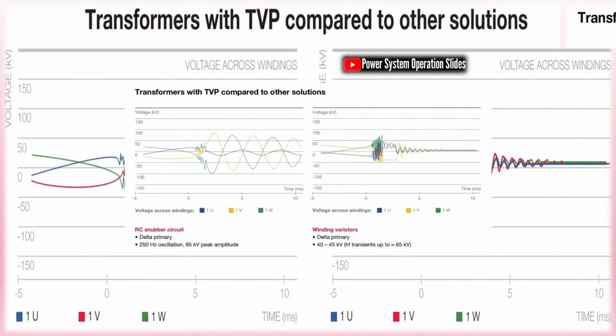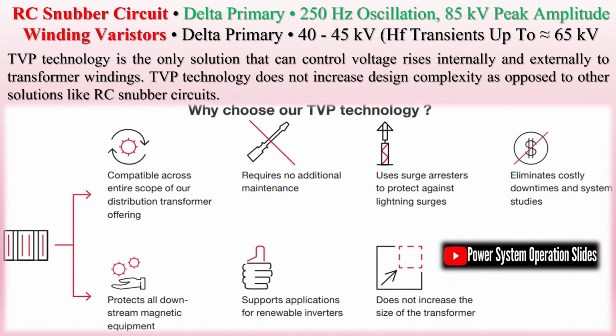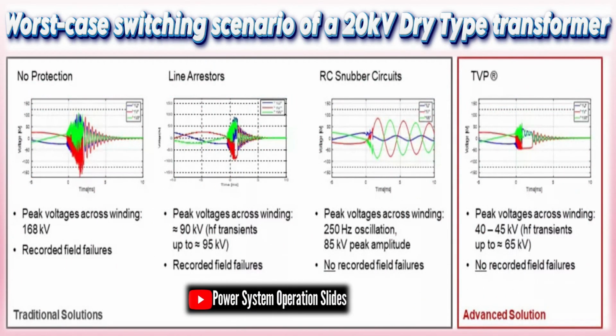However, they are incompatible across all networks and configurations and often expensive to install. A simple solution for a complex problem: transformer with transient voltage protection. TVP technology by Hitachi ABB Power Grids provides complete protection for your electrical systems at every single switching instance. The strategically positioned varistors across the transformer's windings protect them from any overvoltage caused by virtual current chopping and resonance amplification. This prevents voltage peaks from ever reaching levels that could damage the insulation in our transformers equipped with TVP. Moreover, its network-agnostic design makes it the best fit for you, no matter what your needs.